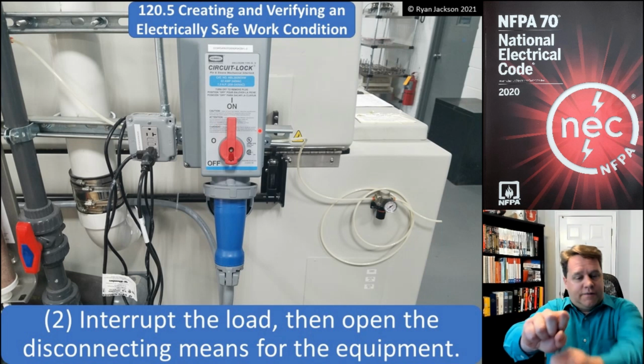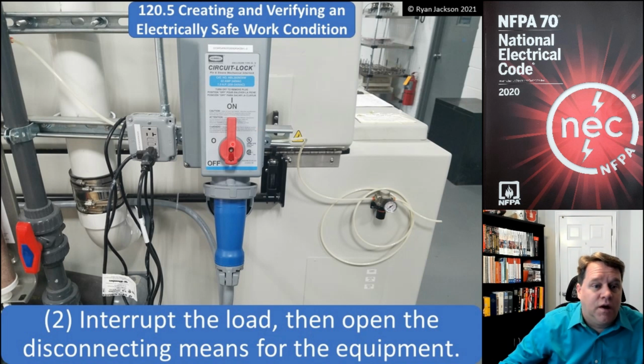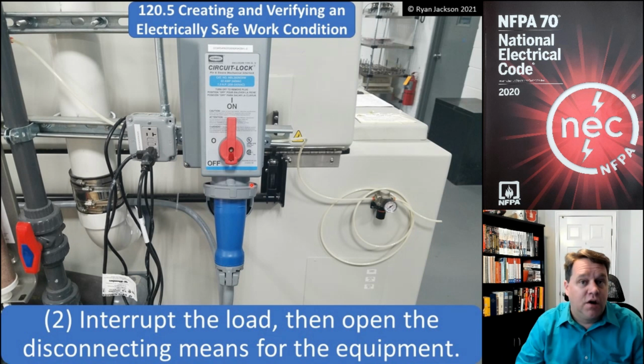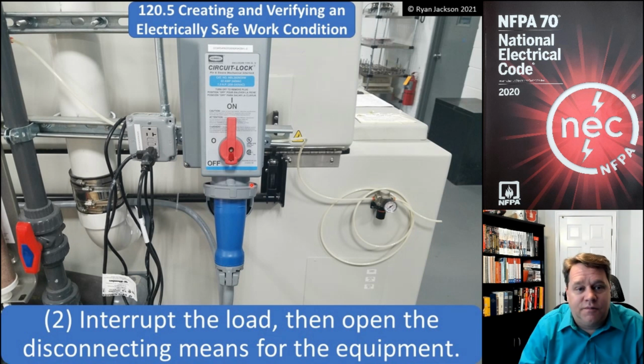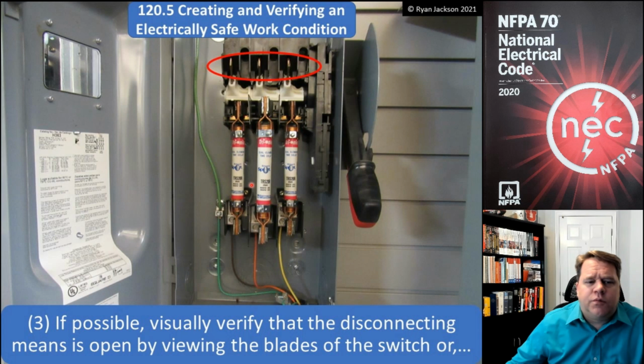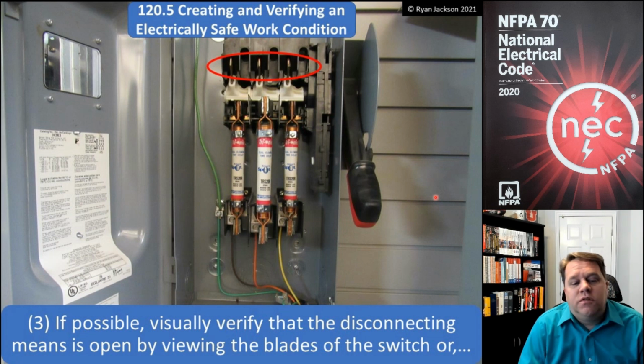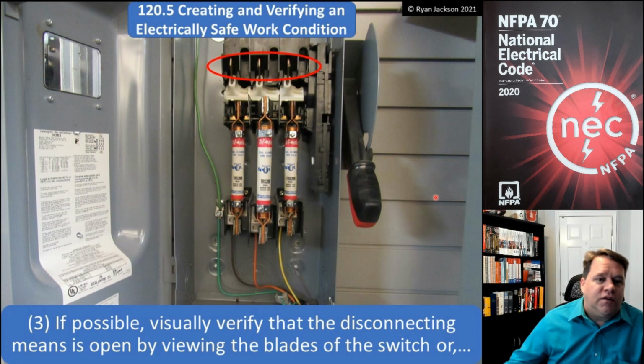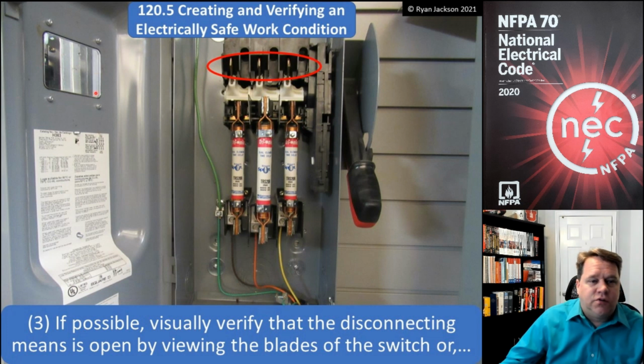You can shut it off and then disconnect it. So interrupt the load, hit the switch, right? And then open the disconnecting means, unplug it, whatever that might entail. Item 3, if possible, visually verify that the disconnecting means is open by viewing the blades of the switch. In this disconnect, you can see that we've got a little window here that allows us to look through it and verify that the blades are in the open position.